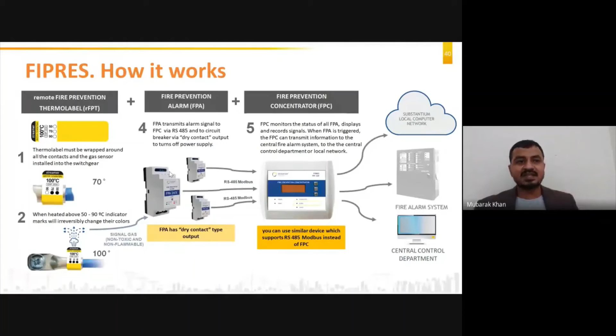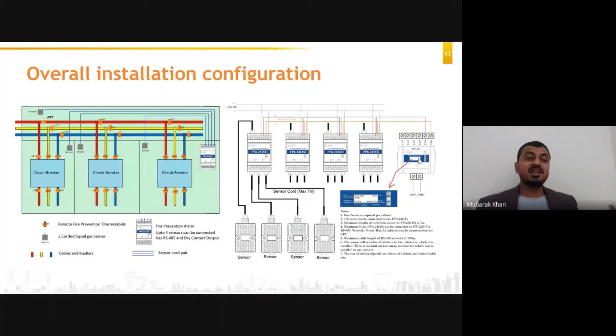This is an electrical system layout. Just to explain, I have taken an example of a panel with one incomer panel, 2 outgoing, and 1 busbar compartment. Stickers will be placed at the incoming and outgoing of the circuit breaker. As you can see, the orange strips are all the RFPTs. Then we have used a multi-channel FPA. In a multi-channel FPA, the sensors will be placed inside the compartment: 1 sensor, 2, 3, 4 sensors. These sensors will be connected to the FPA. Multiple FPAs will be connected together through an RS-485 network, which can be connected to FPC via RS-485. So this is the electrical configuration, just for you to visualize more easily how it works.